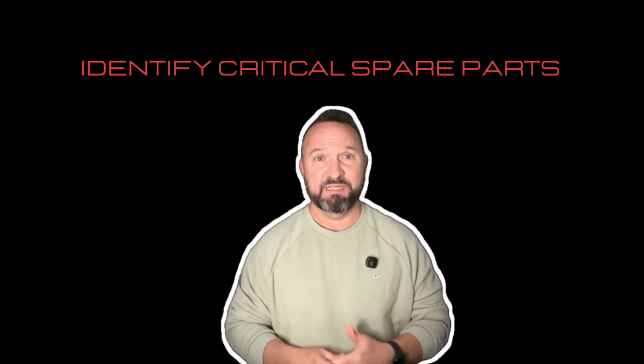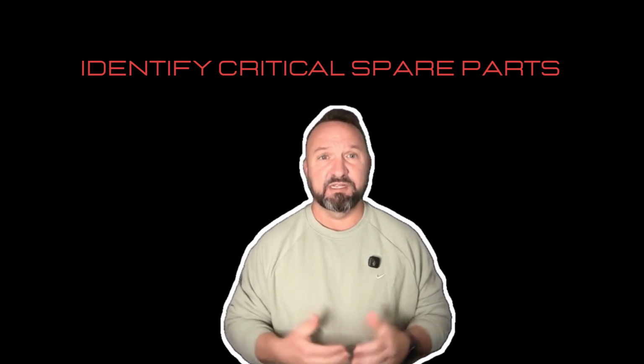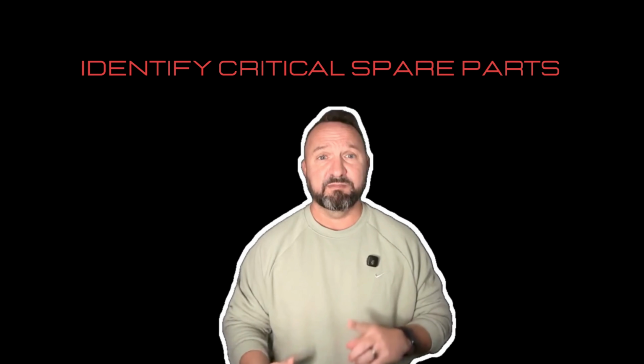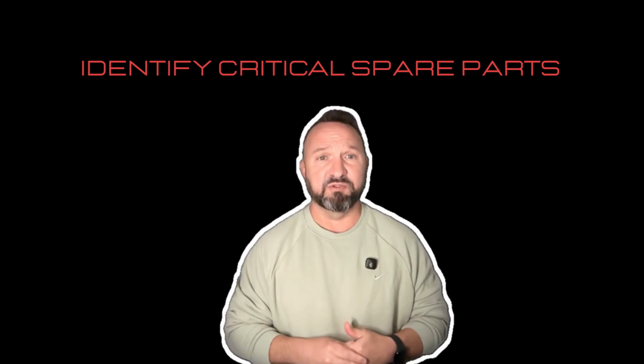Another preventive option that should be considered very early on is identification of critical components that could shut down production. Typical critical spares include control boards, power stacks or IGBT modules, cooling fans, communication cards, battery management system, or contactors. It's important to understand what those critical components are and to have the proper amount of spares based on your portfolio.